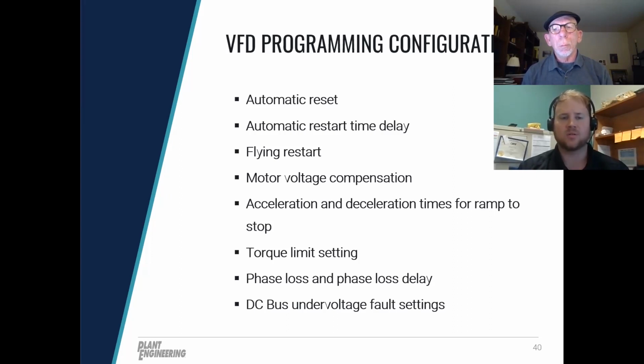If the outage is a temporary outage or a long outage, above 3 seconds, above a couple of minutes, whatever, there's not much you're going to be able to do there. You're shutting down, plant shutting down. But these ride-through programming techniques should help you get through some short-duration voltage sags where you're still going to be seeing 70, 80, 90% at the input terminals.